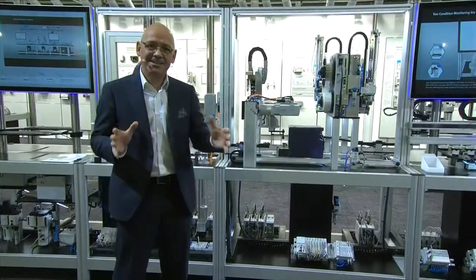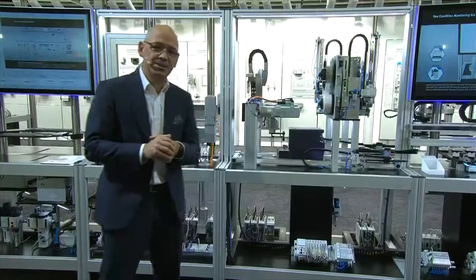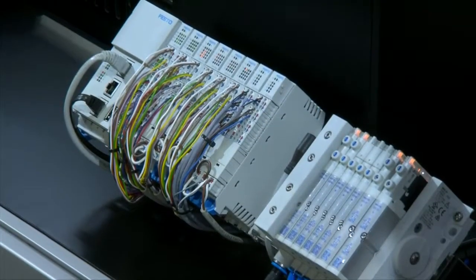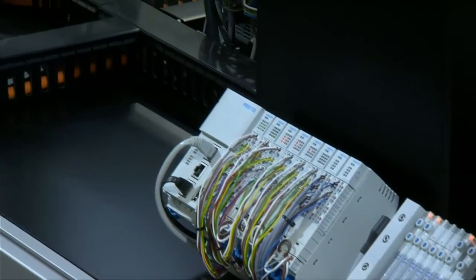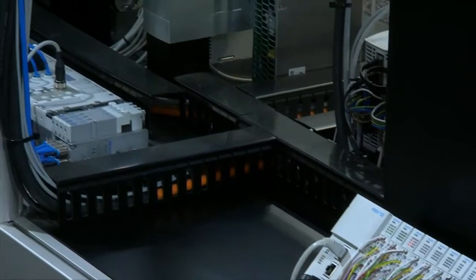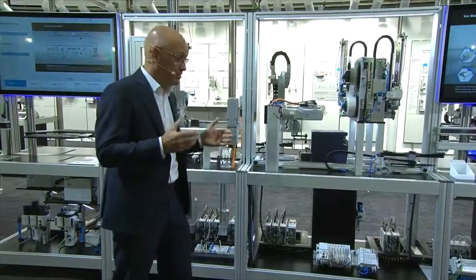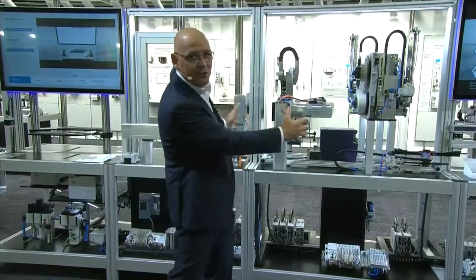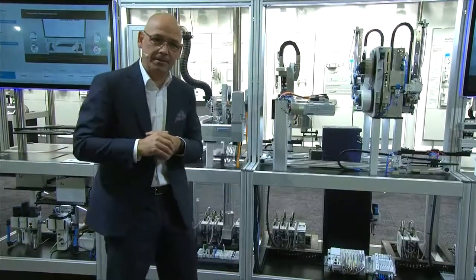Having discrete control on each cell reduces the load on the supervisory PLC and takes the cyber-physical intelligence down to each individual cell. This means if we want to change a cell out for a different function, it's very easy because the control is completely within that cell.